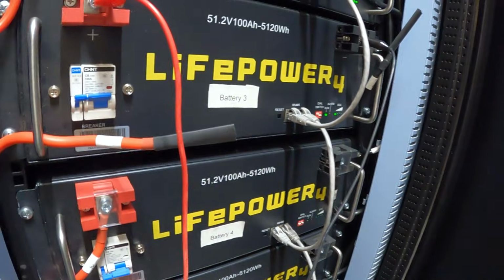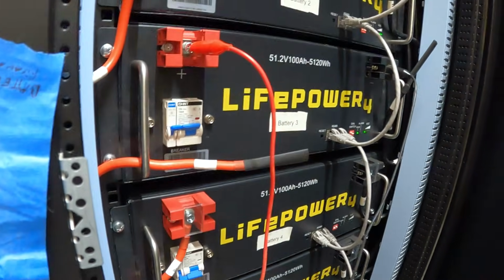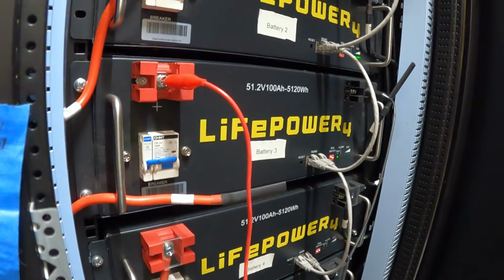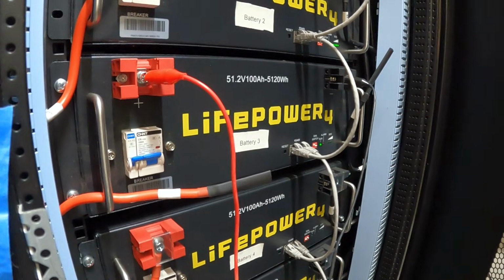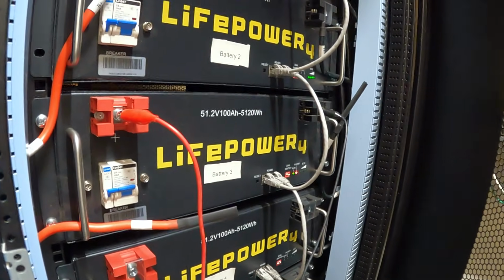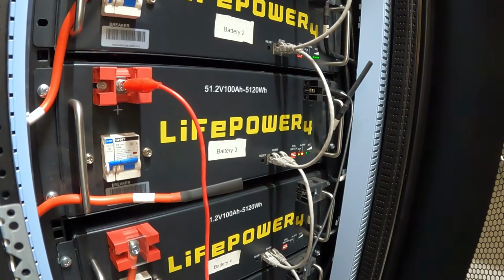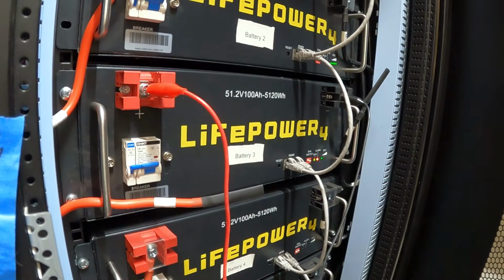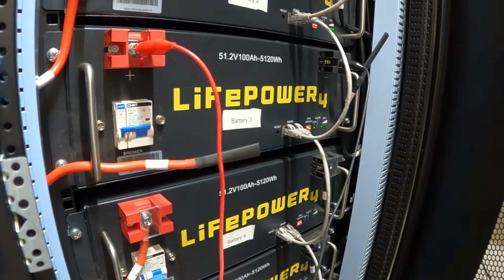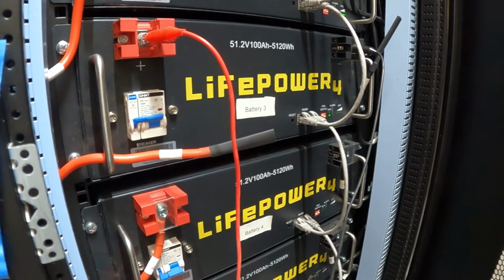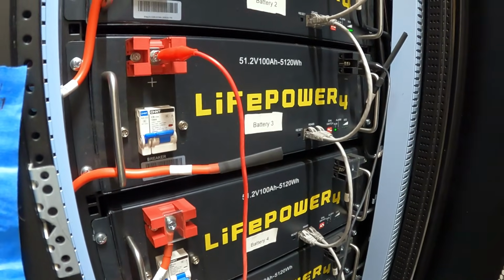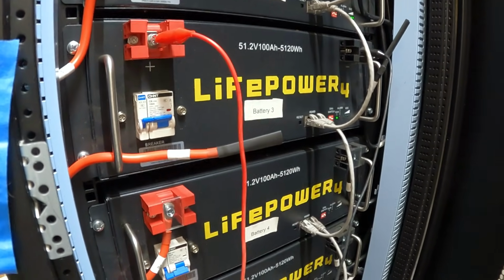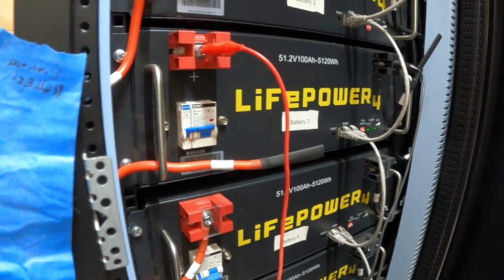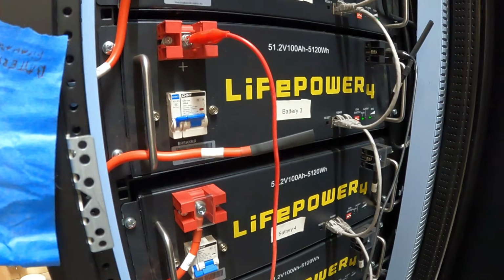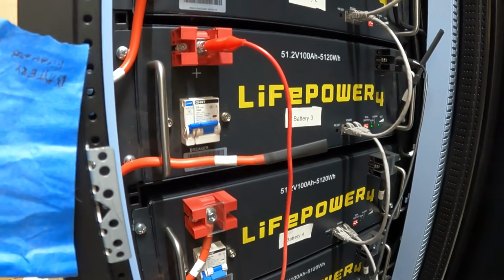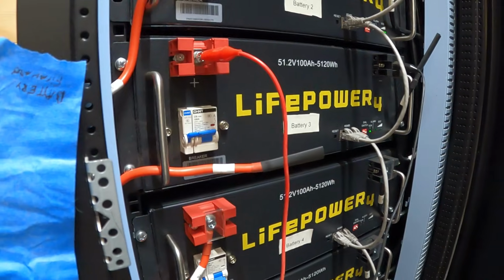But if the inverter's off, that means that Starlink is off, which means I can't monitor anything. That's one of the reasons I knew something was wrong, because I couldn't connect to anything. So first thing you got to do is warm it up. You got to warm up the building, and since the sensors are inside the batteries inside this pack, it takes a while. It can take overnight for them to warm up enough to clear the low temperature.